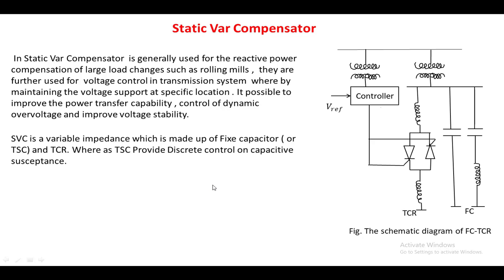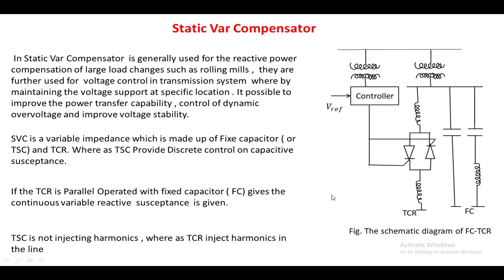In SVC, if a fixed capacitor is used alone, it supplies reactive power in a discrete manner. However, if a thyristor controlled reactor is added along with the capacitor, it provides continuous variable reactive power to the line. The thyristor switched capacitor does not generate harmonics in the line, whereas the TCR injects harmonics.